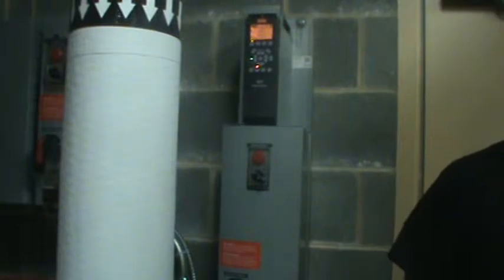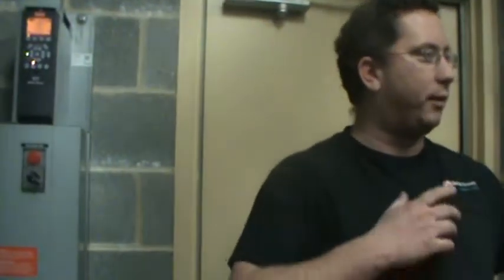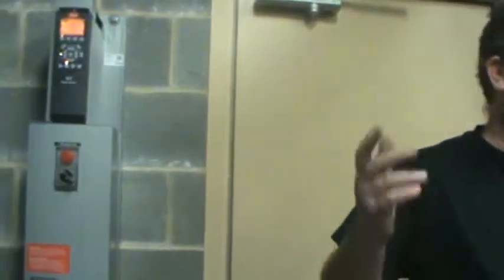You guys have a redundant pump. You guys have the backup. One of these fails, run your other one. You still have your automation. You still have your varying speed, the system you guys designed and bought for. That's what I normally recommend. If one fails, run the other one, get it fixed. You know what hits the you know what? You put the bypass, and you go.